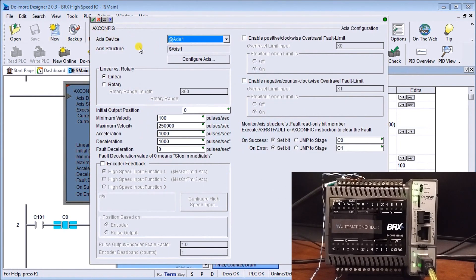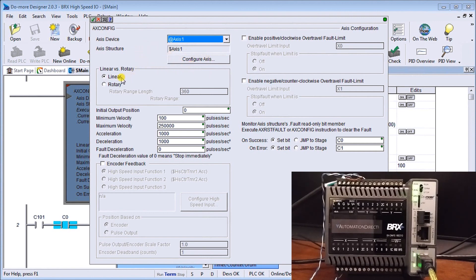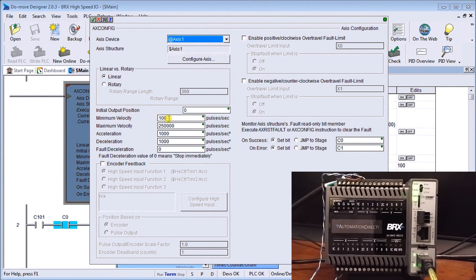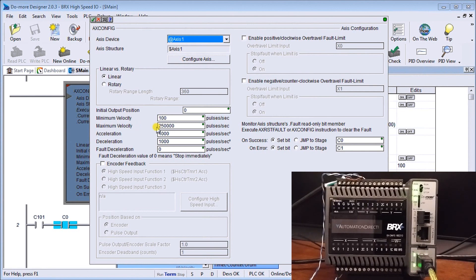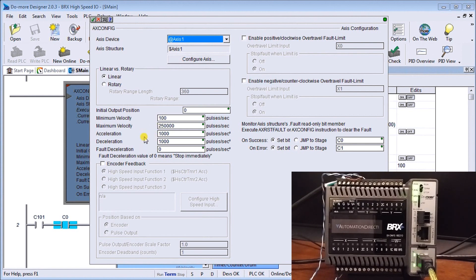We configure our axis here if we wanted to, we said it's a linear, our initial position is zero, our maximum velocity, our minimum velocity is going to be 100, our maximum velocity is going to be 250k or 250,000 pulses per second that we're going to send out of this port and our acceleration and deceleration rate are going to be set at 1000.